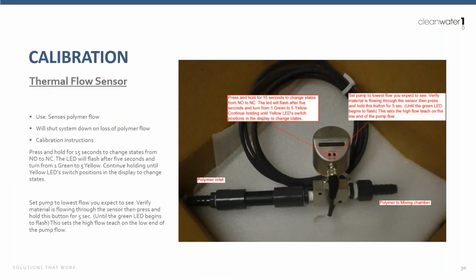Another item that is really common for these systems is what's called a thermal flow sensor. The purpose of this sensor is to sense polymer flow. This thermal flow sensor will shut the system down upon loss of polymer flow. This is really important because this device helps protect the pump. For example, a progressive cavity pump cannot be run dry. So if the system senses a loss of polymer flow, it's going to shut down the system automatically.